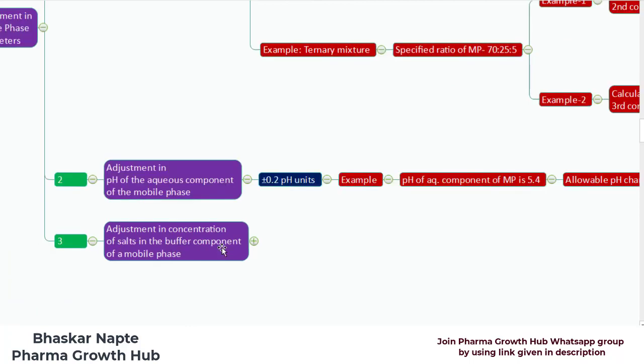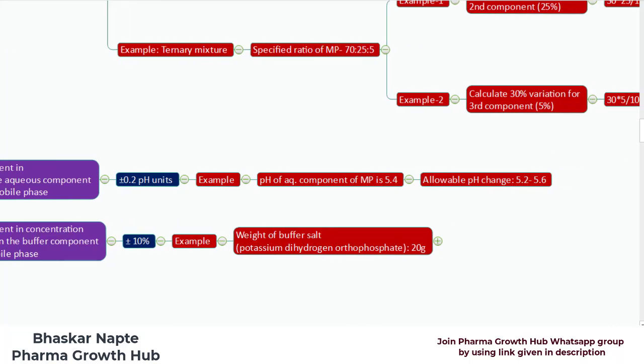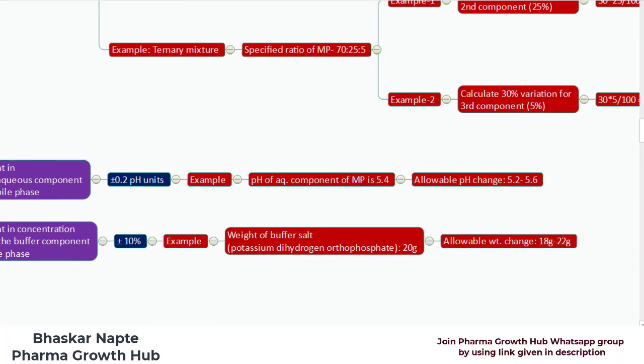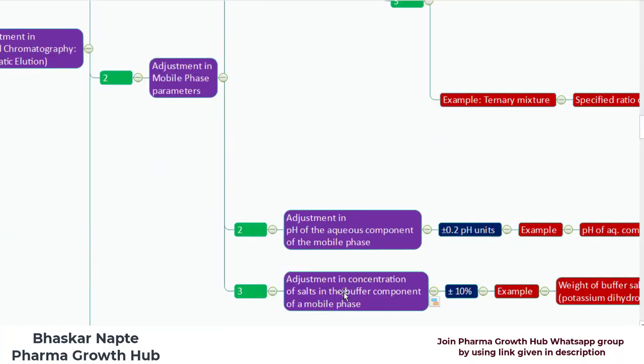The next point is adjustment in concentration of salts in the buffer component of a mobile phase. You can make an adjustment of plus or minus 10%. For example, if you have a buffer consisting of potassium dihydrogen orthophosphate and the weight of the salt is 20 grams, calculate 10% of 20 grams, which is 2 grams. So plus or minus 2 grams is the allowable variation, making it 18 grams to 22 grams. These are the important points when it comes to adjustment in mobile phase parameters.